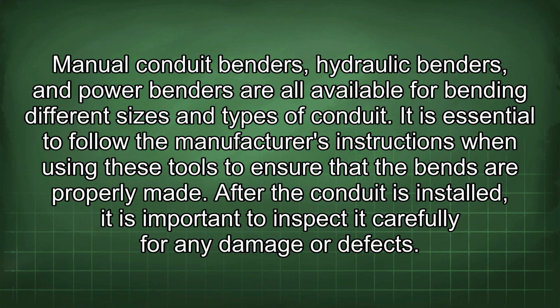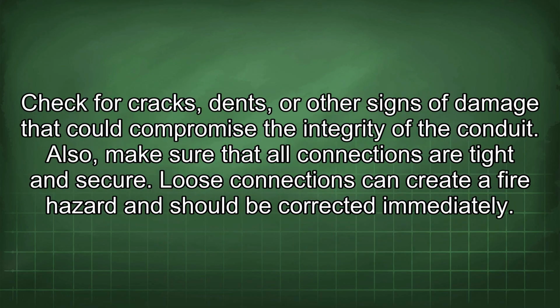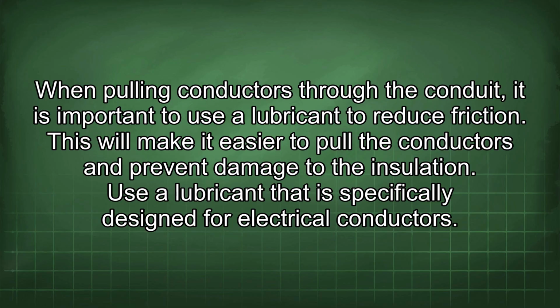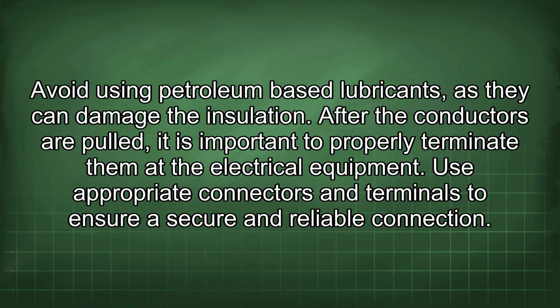After the conduit is installed, it is important to inspect it carefully for any damage or defects. Check for cracks, dents, or other signs of damage that could compromise the integrity of the conduit. Also, make sure that all connections are tight and secure. Loose connections can create a fire hazard and should be corrected immediately. When pulling conductors through the conduit, it is important to use a lubricant to reduce friction. This will make it easier to pull the conductors and prevent damage to the insulation. Use a lubricant that is specifically designed for electrical conductors. Avoid using petroleum-based lubricants as they can damage the insulation.